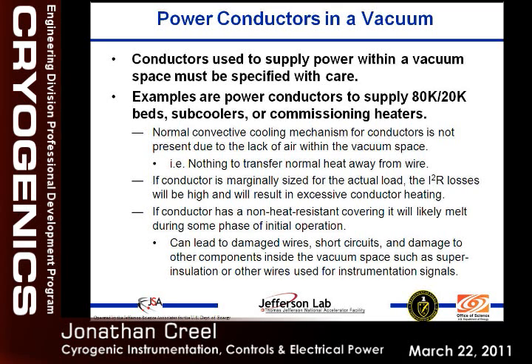It allows more area to dissipate that heat, so you don't get buildup and heat concentrations that will melt the wire. The other thing is you obviously want to use something like a glass insulation or Teflon in some cases, but you definitely don't want to use thermoplastic.